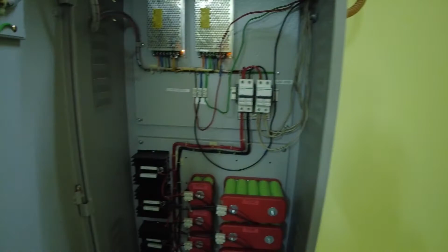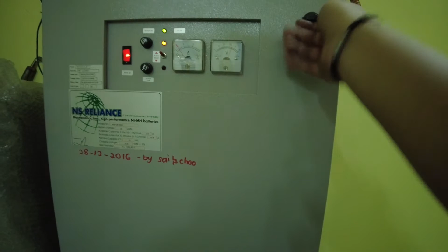Hi, this is the 11 kV main HV room. It's located just next to the LV room. Currently I'm inside here just to do a routine check. Okay, let us have a look at what to check. First of all, we have the tripping unit. Okay, this is using dry cell. They have a double charger. Okay, the voltage is alright, charging amp is okay. Alright, it's dry, free from moisture.